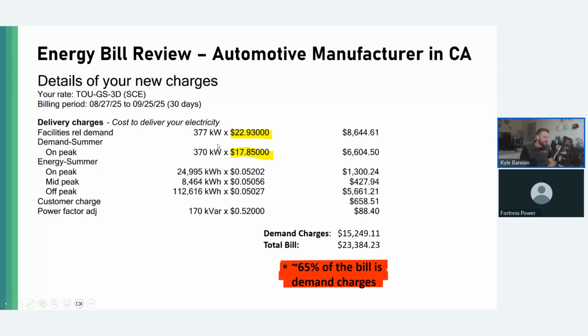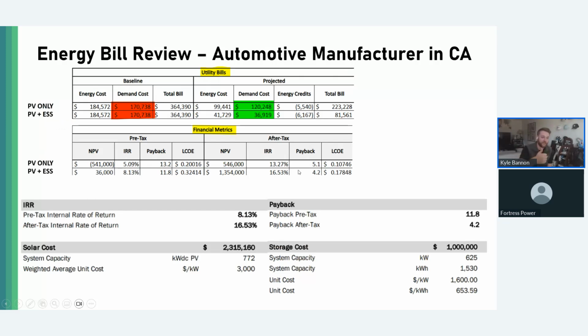This bill has some of it at certain times of year above that $20 per kW threshold, but below it at other times. The other rule of thumb I use is if over half your bill is made up of demand charges. In this case, 65% were demand charges and the rest were normal time-of-use usage charges. You need to be looking at a battery for peak shaving purposes. This was a perfect example, with demand rates right around $20 per kW, and demand making up 65% of their bill.